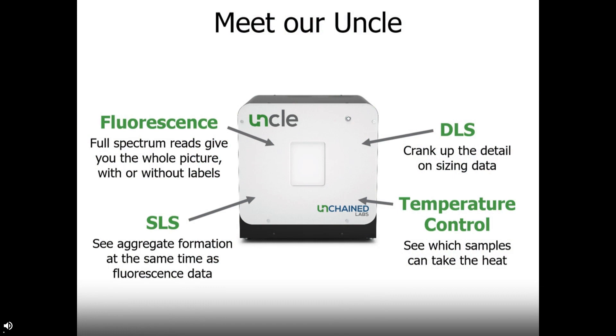UNCLE is an all-in-one stability platform ready for AAV. It uses two lasers to excite either label-free capsid protein intrinsic fluorescence or a variety of dye-based fluorescence — we'll actually use both methods to look at AAV stability. With full-spectrum fluorescence detection, UNCLE can pick up on both kinds of those signals, which is really valuable. SLS is the scattered light from those two lasers and gives information on what aggregates form, especially during a thermal stability ramp. DLS is dynamic light scattering and allows for detailed measurements of size and size distribution. Those three detection methods can be operated isothermally or across a heat ramp designed to thermally stress samples and see which ones can take the heat.